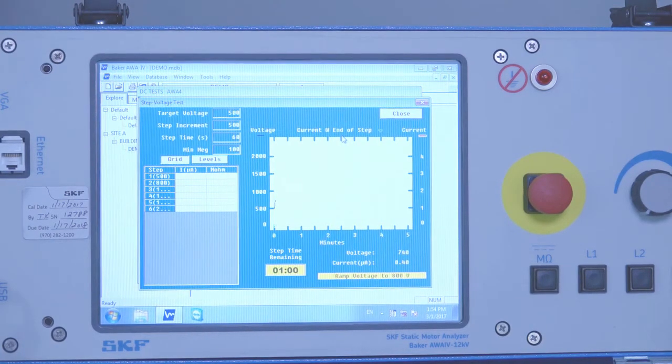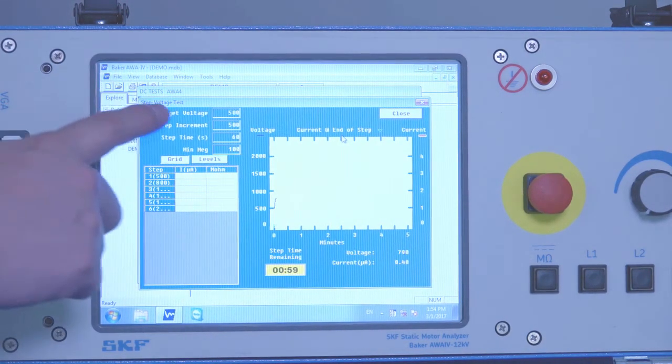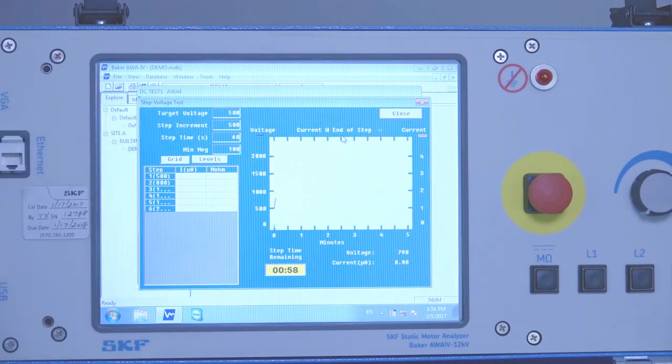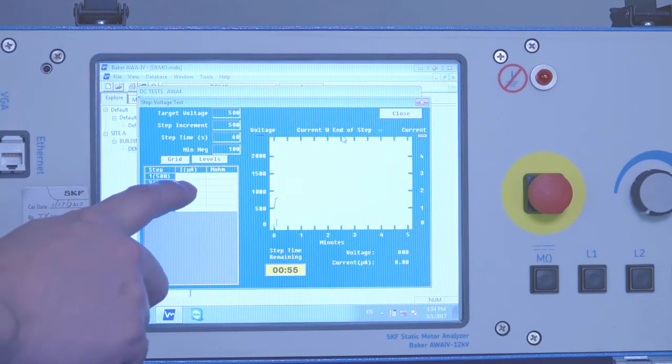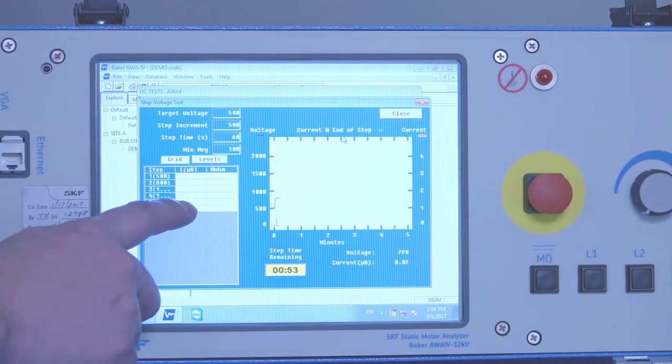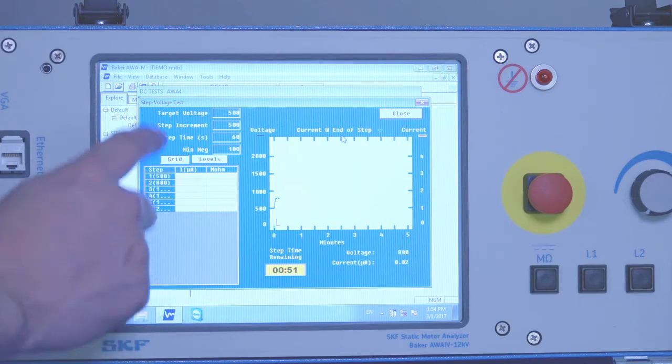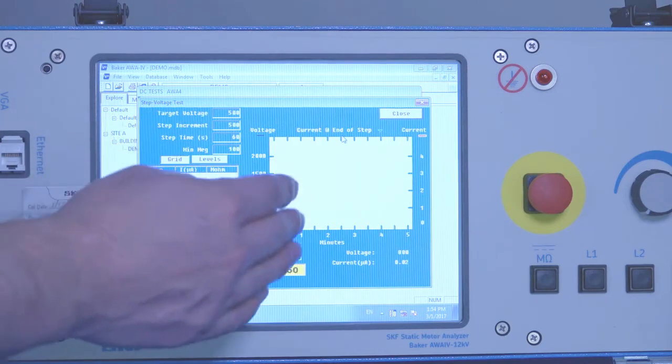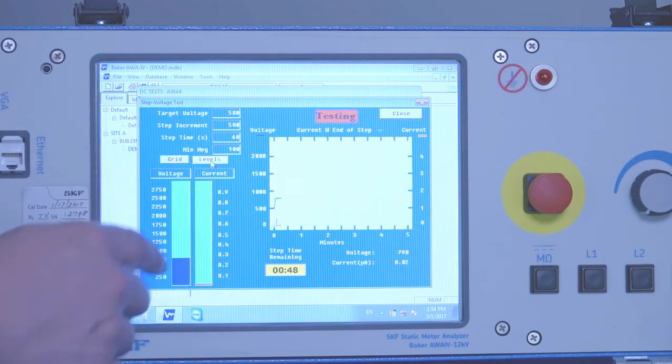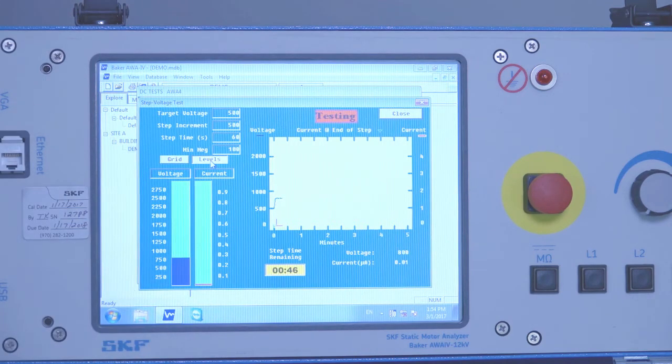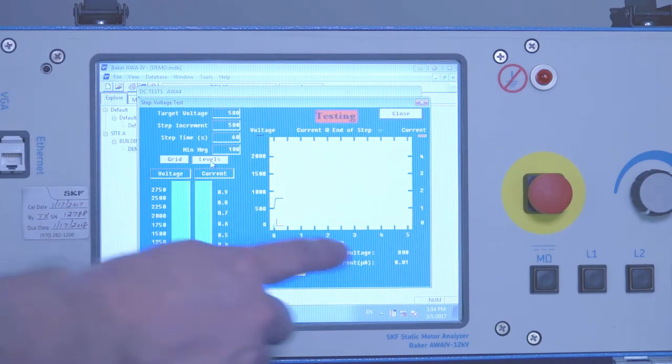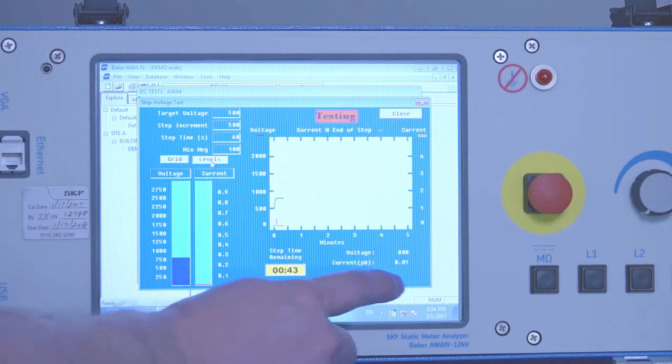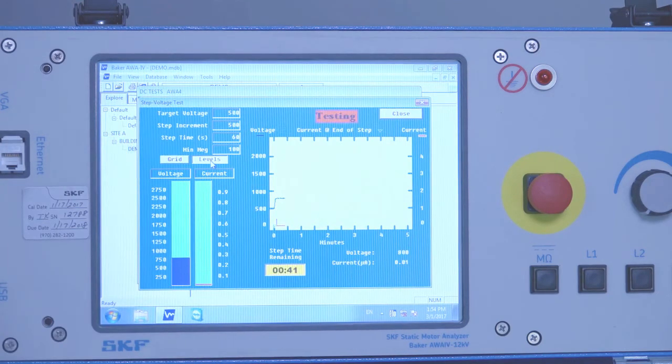Alright, so now we've moved on to the step voltage test and we can see the grid will populate with the leakage current and calculated megohms as we proceed through each step. We can click on the levels screen to see the voltage level and leakage current that we're presently at. You can also see the voltage level and the leakage current here in the lower right hand corner.